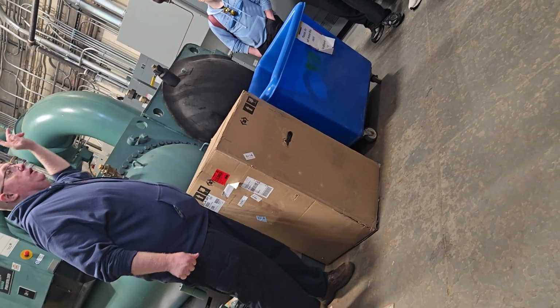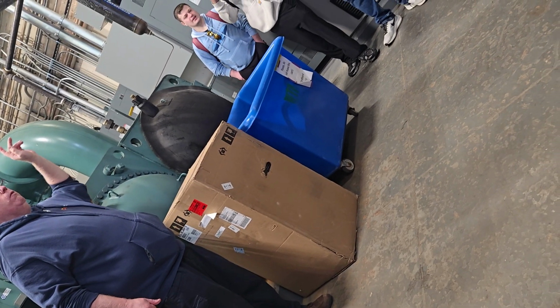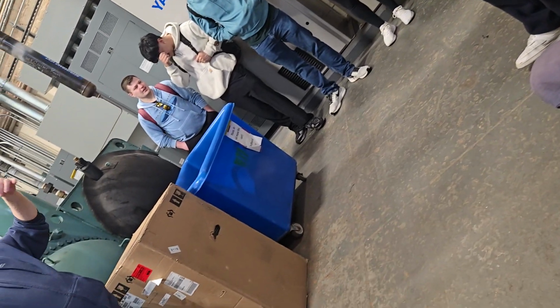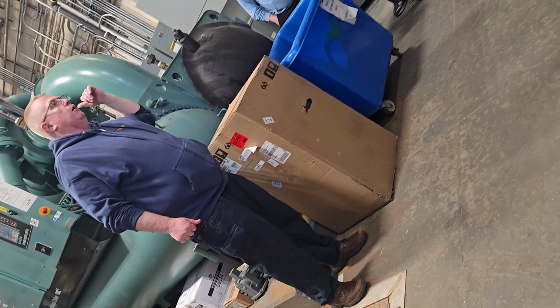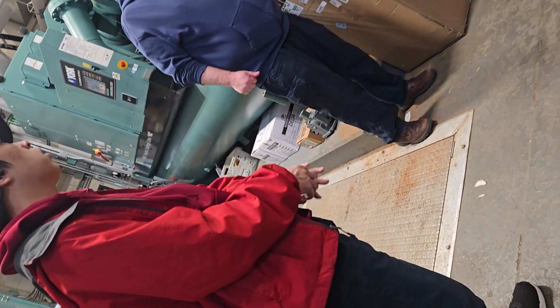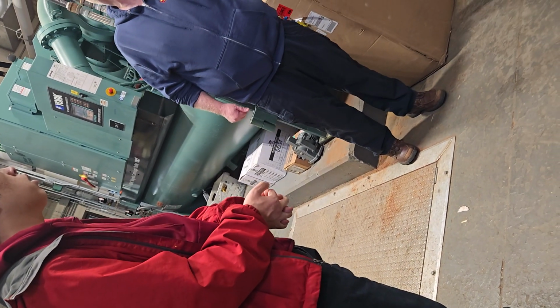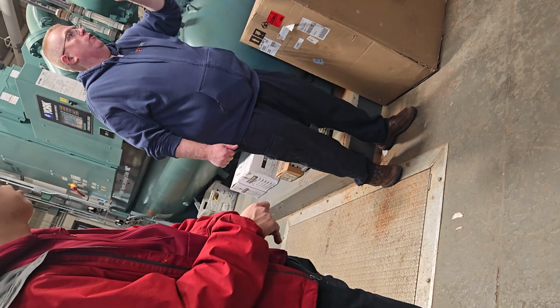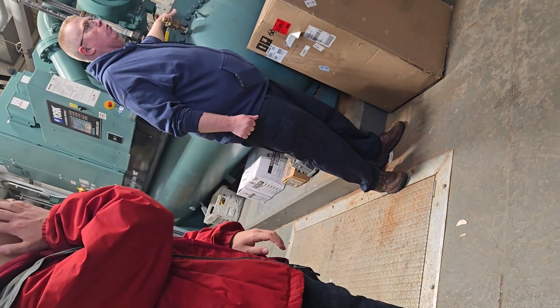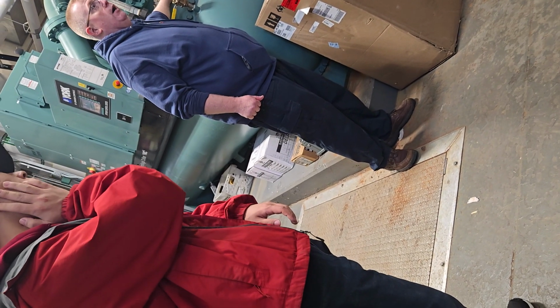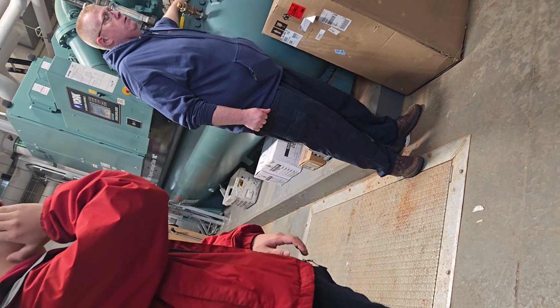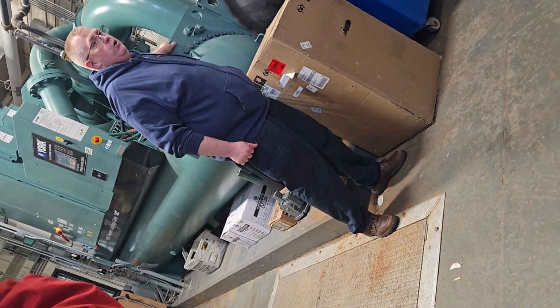We run water down from the cooling towers on the roof, and we reverse the water. We actually take the cold energy from outside air in the winter, and we run it into here to chill the water, which is the chilled water that we would typically manufacture through refrigeration and electric compression.